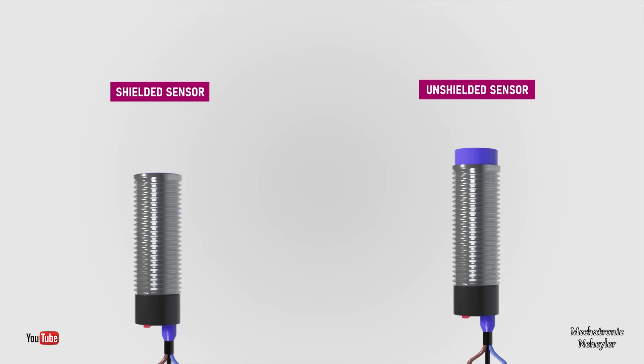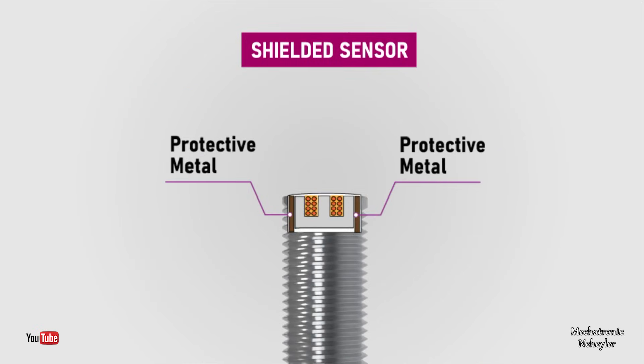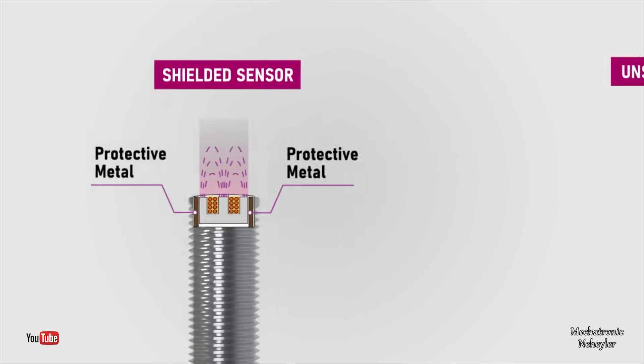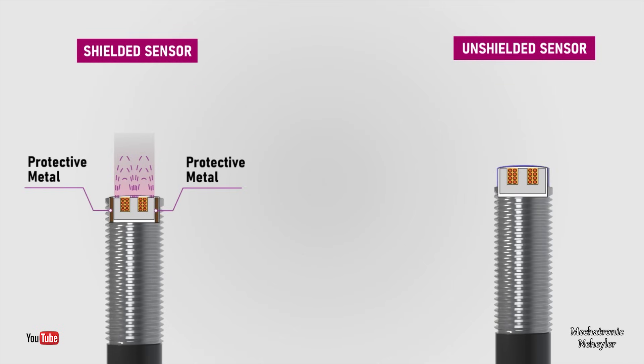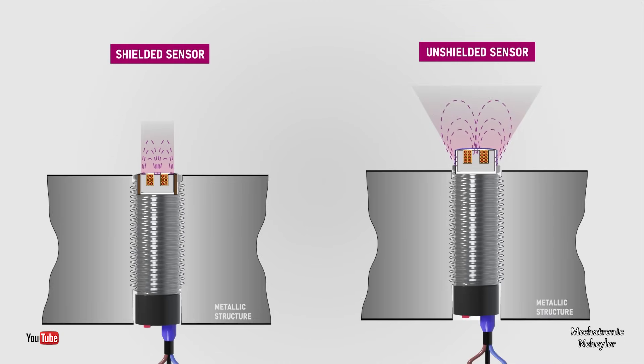Inductive sensors are available in many different configurations. They can be shielded or unshielded. A sensor is shielded if its inner coil has a metallic shield. This shield is cylindrical in shape and covers the entire contour of the sensor coil, limiting detection only to the front of the sensor. The installation of a shielded sensor can be flush — the face of the sensor is flush with the metal structure where it is installed — since the metal structure does not affect its operation.